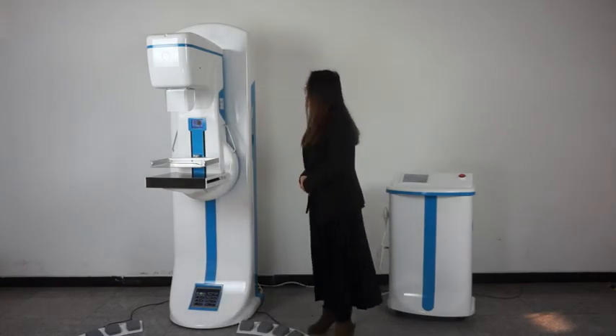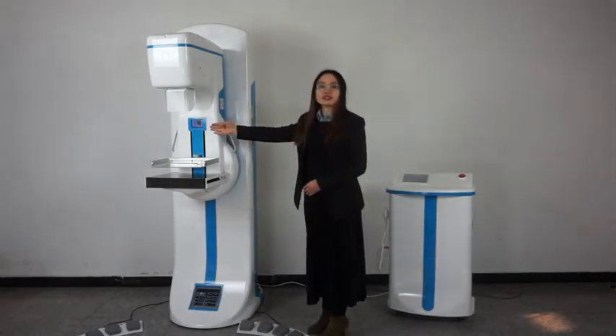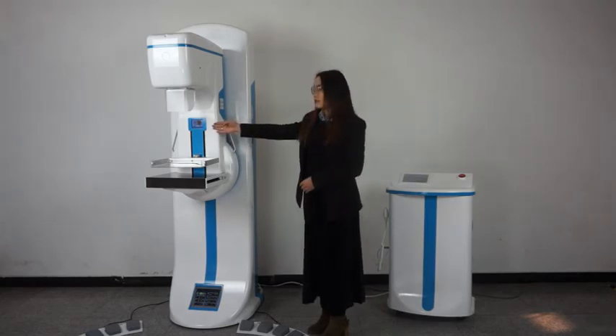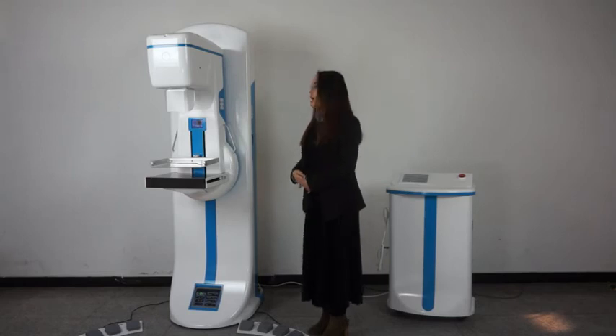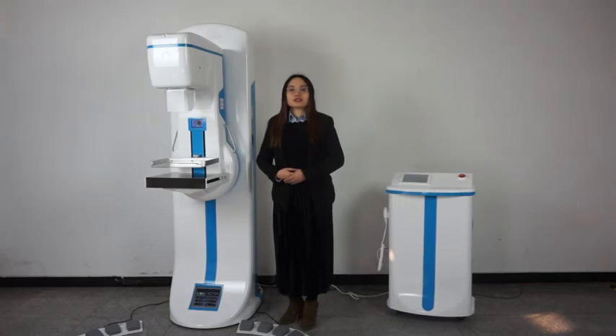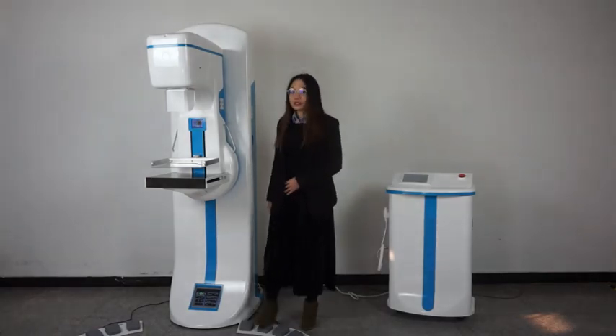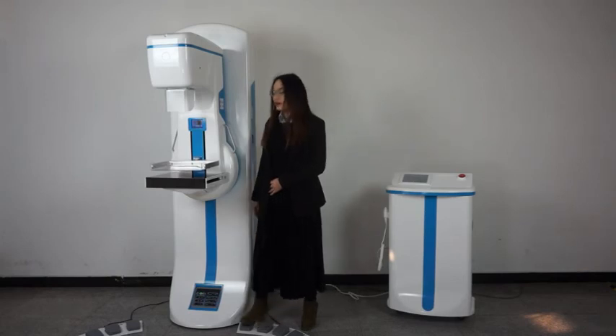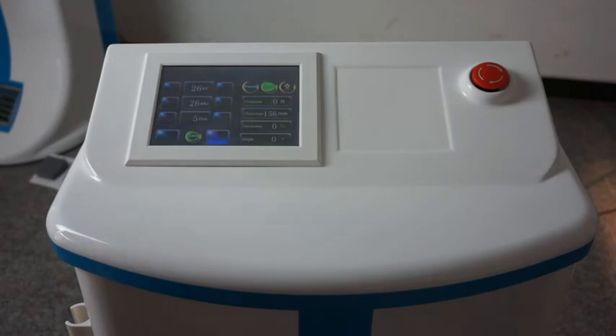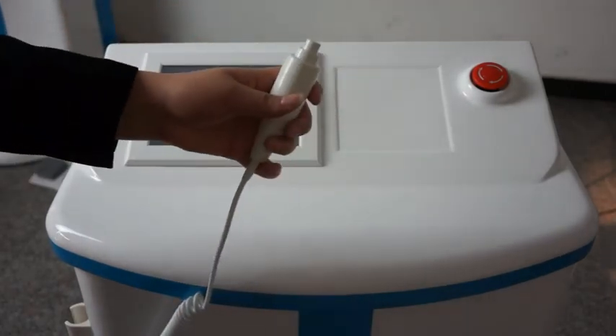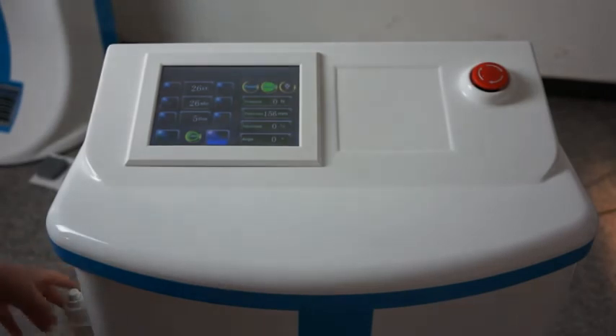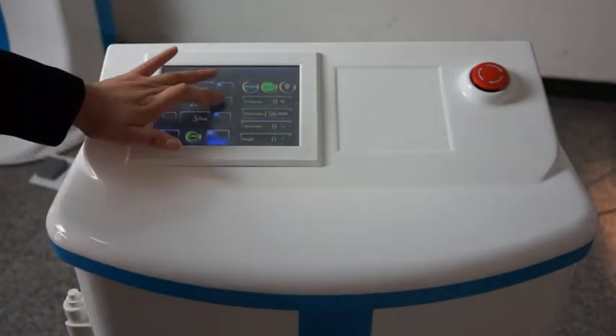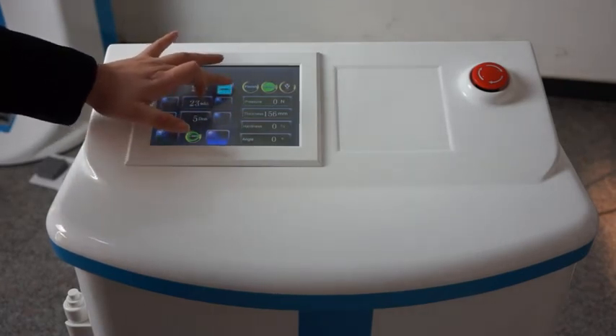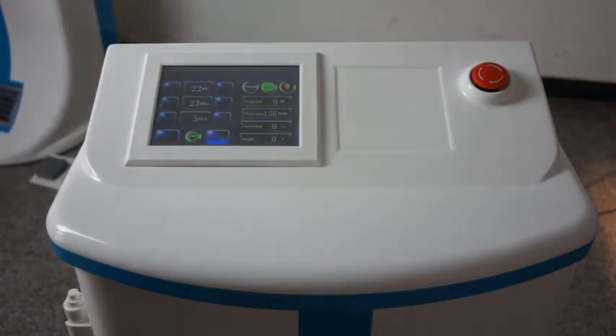Also, doctors can know how much pressure and thickness patients can endure through the LCD screens on the upper and lower parts of the frame. They include mAs, kV, thickness of the mammary gland, and also real-time pressure. At the same time, for the doctor's convenient operation, there are also dual foot brakes to control the compressor down and up. The exposure hand switch is fixed on the control console, where doctors can also adjust mAs and kV here through this 8-inch LCD user interface.